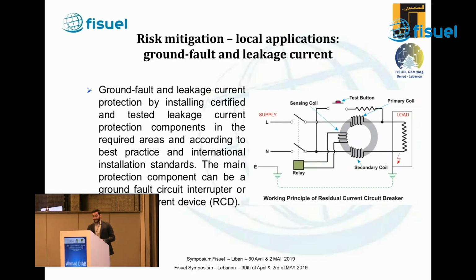For the ground fault and leakage current, devices called residual current devices or ground fault interrupters are used. They basically compare the current going to and coming back from the components, and if there's any difference above a certain threshold, they trip the circuit. To give you some insight about some local issues we faced with this measure, these devices are very sensitive, and they have an issue which is related to nuisance tripping. So they can trip also if you have transient currents to the ground, or in certain situations a high inrush current.